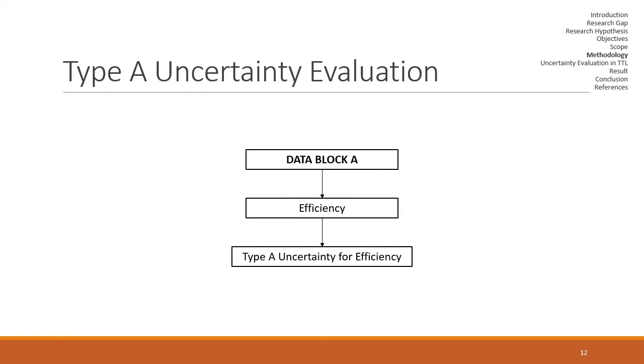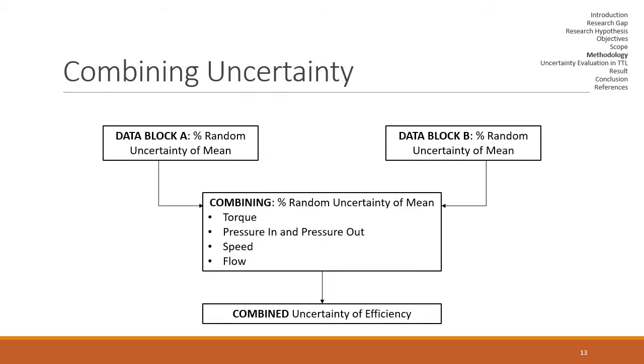Now the data from data block A are used to calculate efficiency of the turbine and type A uncertainty of efficiency. Now we have two percentage uncertainty. Percentage uncertainty from data block A, that is type A uncertainty, and from data block B, that is type B uncertainty. We combine the percentage uncertainty of torque, pressure in and pressure out, speed and flow, and then we get the combined uncertainty of efficiency.